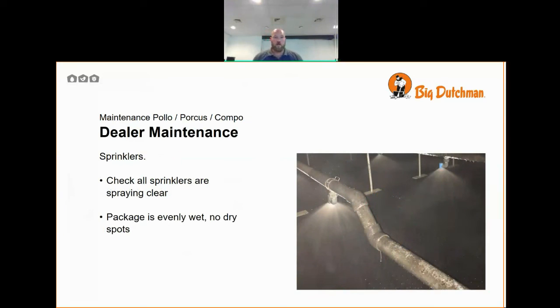Check the sprinklers are spraying clearly and that the package is evenly wet with no dry spots. And any of the sprinklers that are blocked need to be removed and cleaned. This is considered a user level task, but it can also be done by technicians. It's best to take a bucket of clean water up to the sprinkler room with the system off and remove them one by one, cleaning them in the bucket of water, and then refitting.